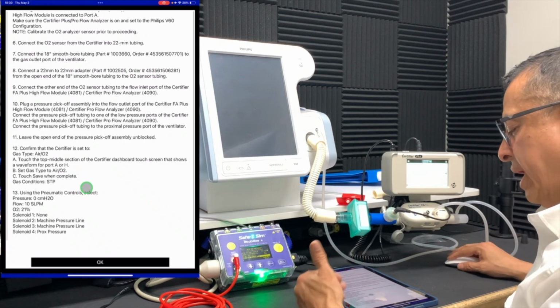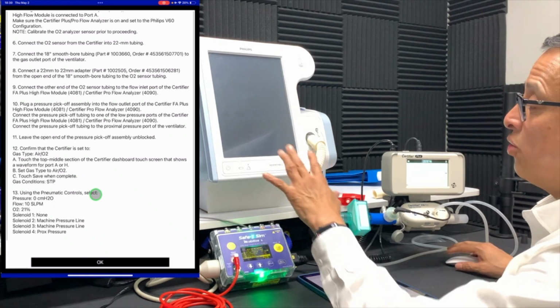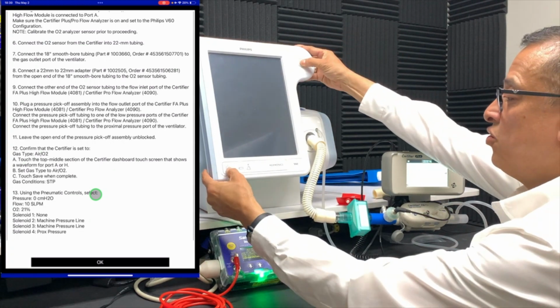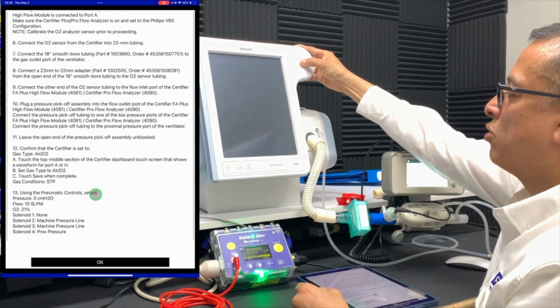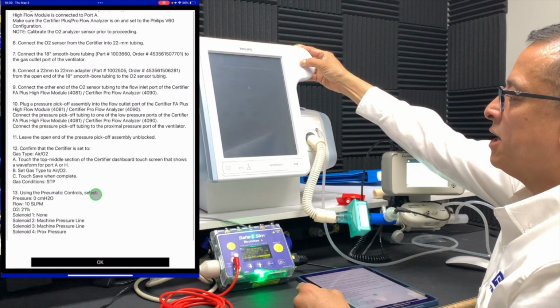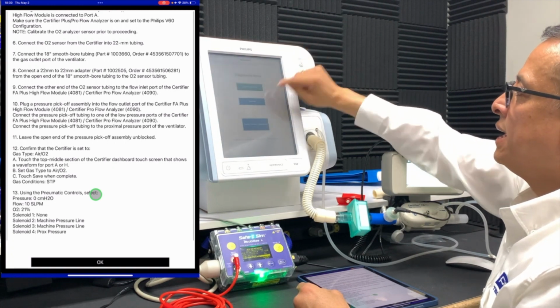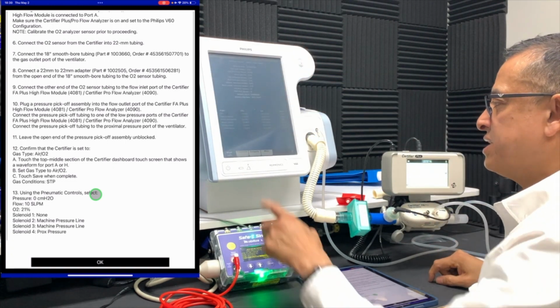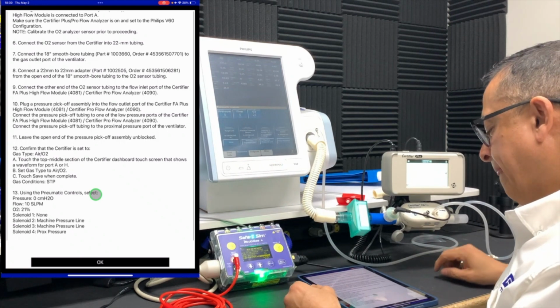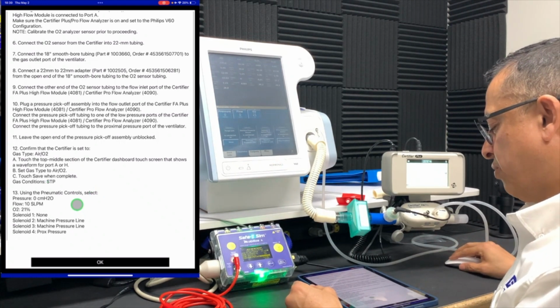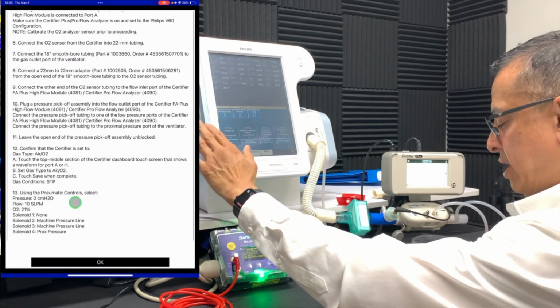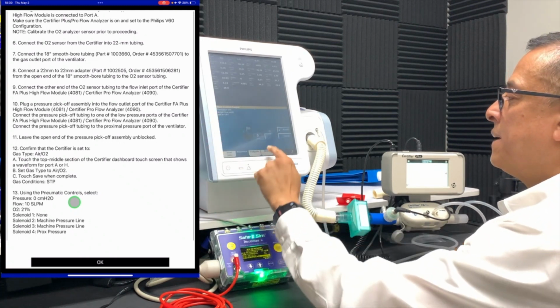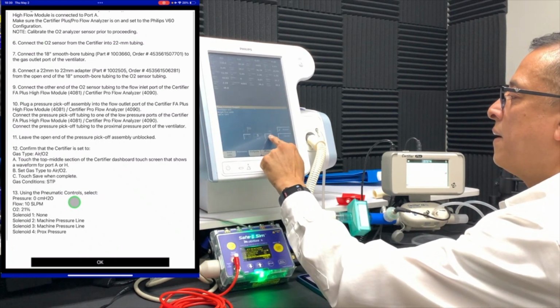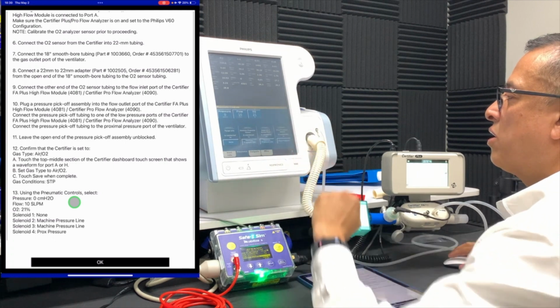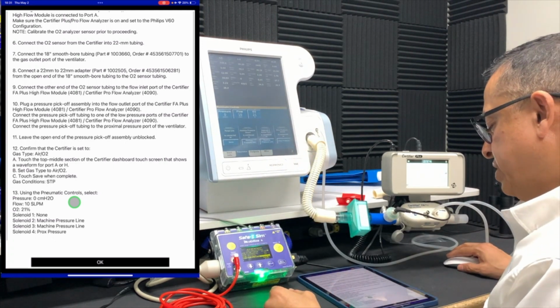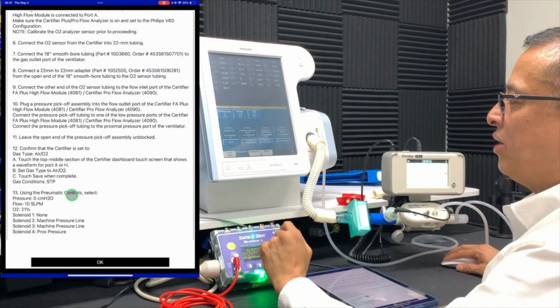And then we also want to now go into the service mode again of the ventilator to do the subsequent tests. So I'll go ahead and do that real quickly. We'll get that set up into service mode. And we now need to configure these settings, going into the pneumatics menu, and we need to configure this flow. So we want to set the pressure to 0, set our flow for 10. Go ahead and do that. Get some flow occurring here. And we want to set our O2 set for 21%, which it is.